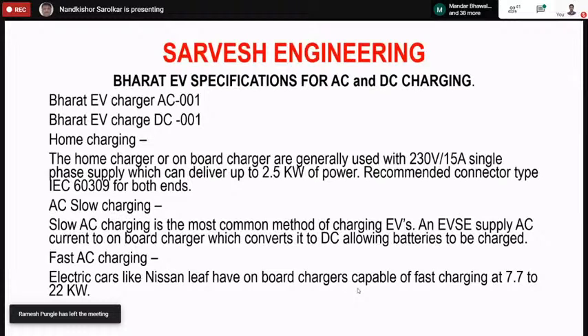DC chargers with 350 kilowatt rating are also operational, mainly in overseas markets. Due to the high power rating, the operating system requires to be a high voltage system like 720 volt or 900 volt, etc. The charging system, including charging cable, needs to be liquid or jelly cooled for effectively removing the heat generated during charging.